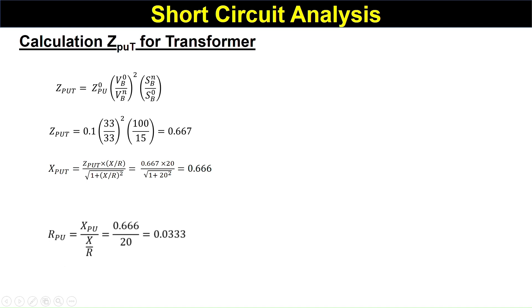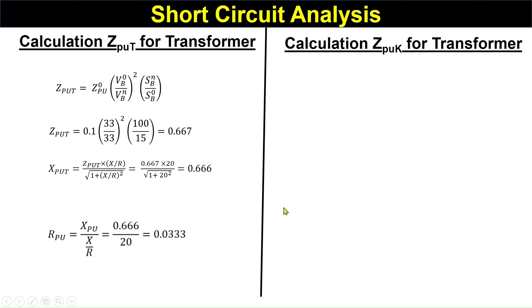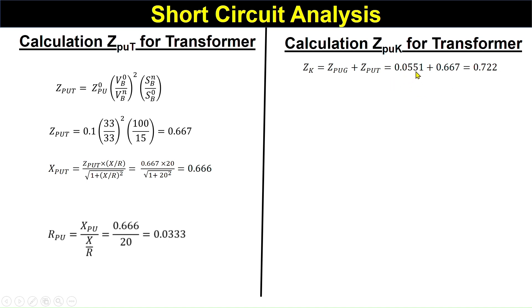R per unit of the transformer equals X per unit divided by the X/R ratio: 0.666 divided by 20 equals approximately 0.0333. Now we calculate Z_k, the total per unit impedance up to the fault point. We have considered the fault on the 11 kV bus (bus 2). Z_k equals the per unit impedance of the grid plus the per unit impedance of the transformer: 0.0551 + 0.667 = 0.722 per unit.